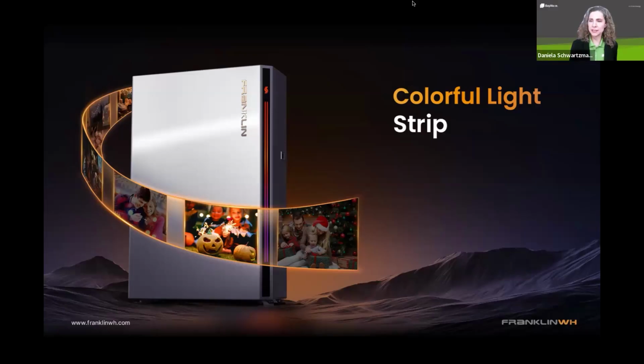Do you have a stacking kit available? No, we do not have direct sandwich stacking. We do have a freestanding mount where the batteries, per our UL 9540A report, can be installed one in front of the other with 2.3 inches between units. That is if the AHJ accepts the UL 9540A report—not all do, like LA County. But with the freestanding mount, you can get many batteries in a much closer area than if you had to install them laterally on a wall.